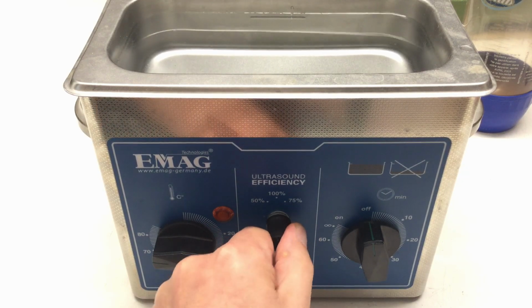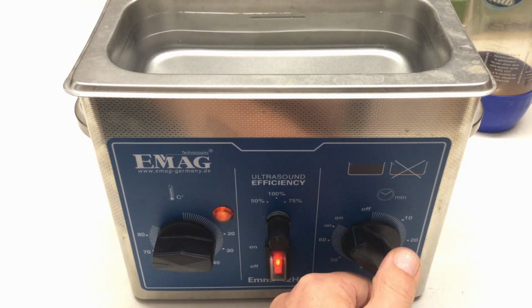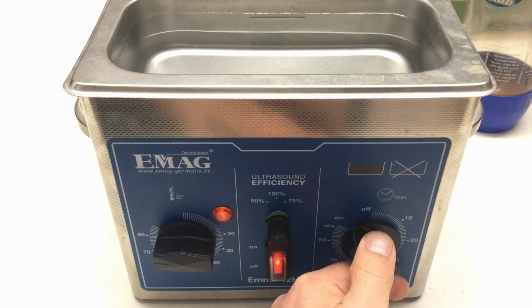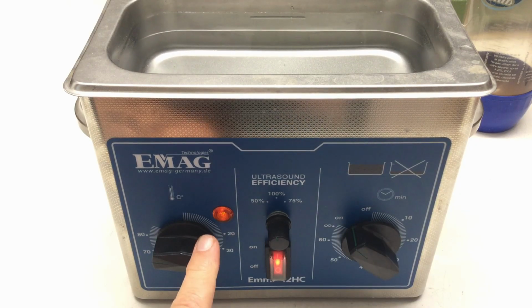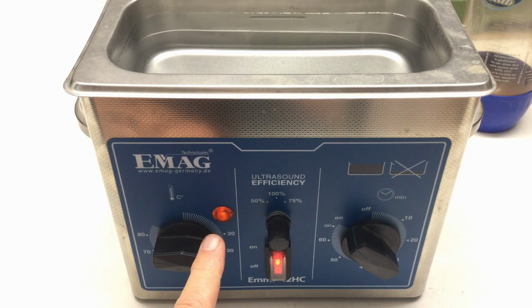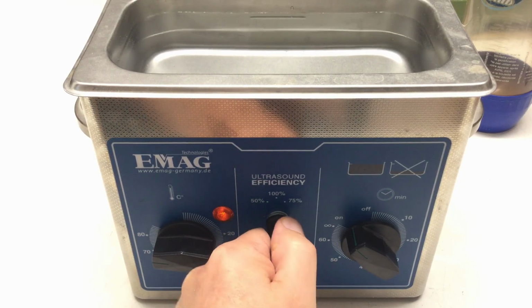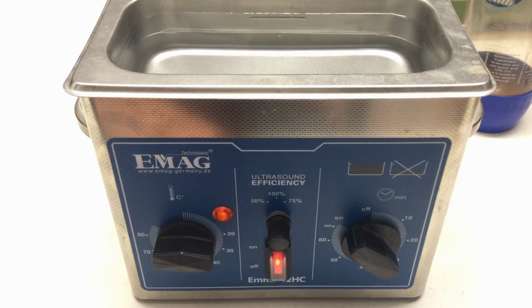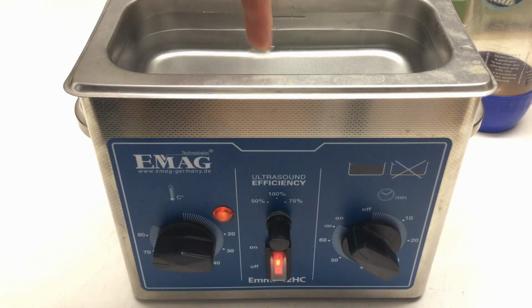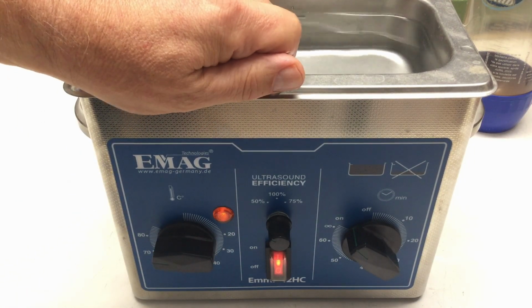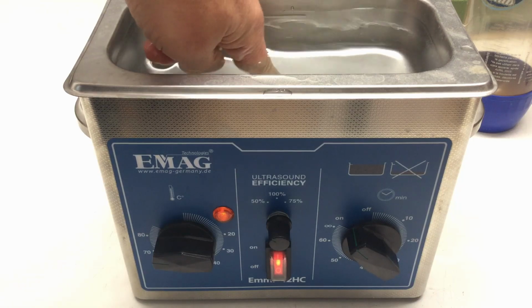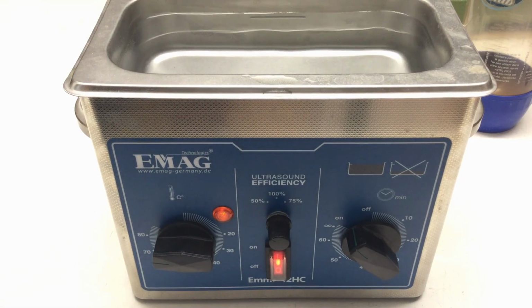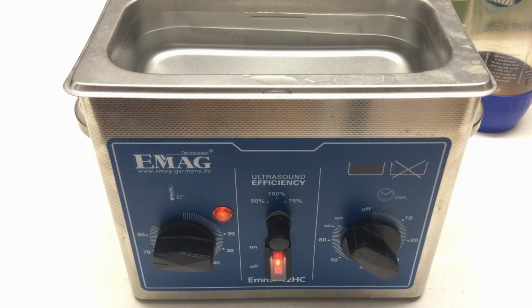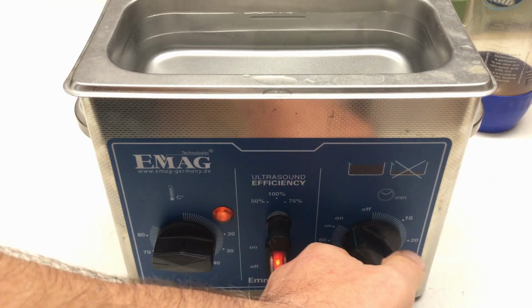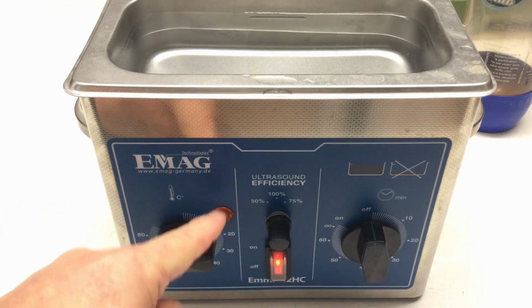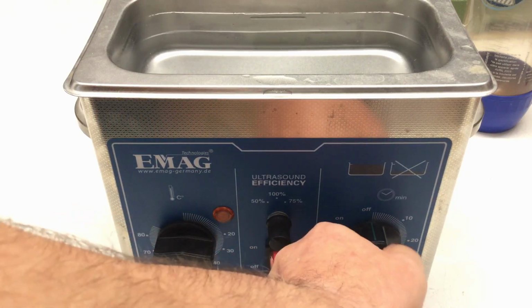So in conclusion, neither the heating works nor the ultrasound - that is, we haven't checked another. Oh look, now the heating is on, but still no ultrasound. The light came on, okay, operator's error, but still no cleaning action. I thought this would be easy, but no. And I can feel the heat now coming on here. This is not a mechanical failure of the timer, because otherwise it wouldn't ding and it wouldn't switch on the heating.